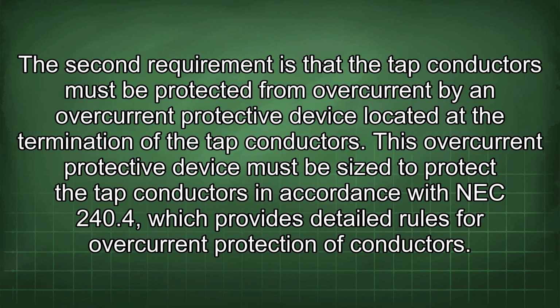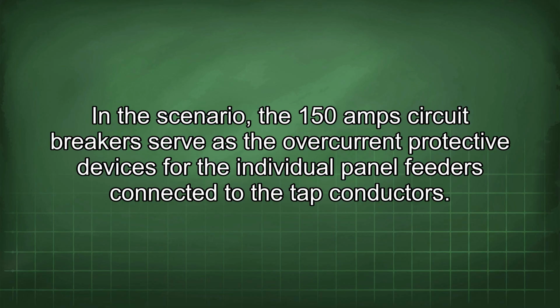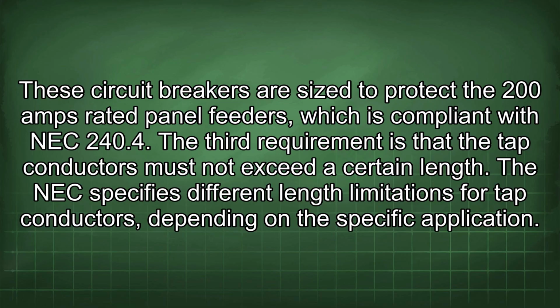The second requirement is that the tap conductors must be protected from overcurrent by an overcurrent protective device located at the termination of the tap conductors. This overcurrent protective device must be sized to protect the tap conductors in accordance with NEC 240.4, which provides detailed rules for overcurrent protection of conductors. In this scenario, the 150 amp circuit breakers serve as the overcurrent protective devices for the individual panel feeders connected to the tap conductors.